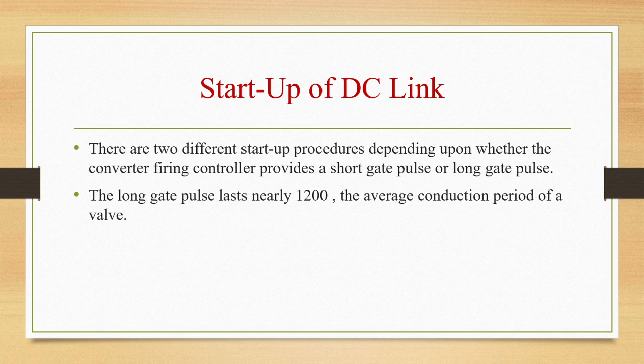Starting sequence in this case is as follows. First is deblock inverter at about gamma equal to 90 degrees. Second is deblock rectifier at alpha equal to 85 degrees to establish low direct current. Third is ramp up voltage by inverter control and the current by rectifier control. Let us see next startup with short pulse firing.